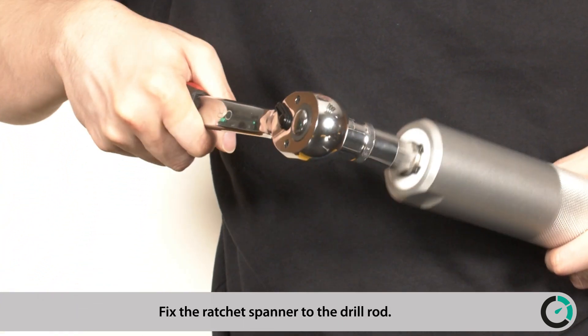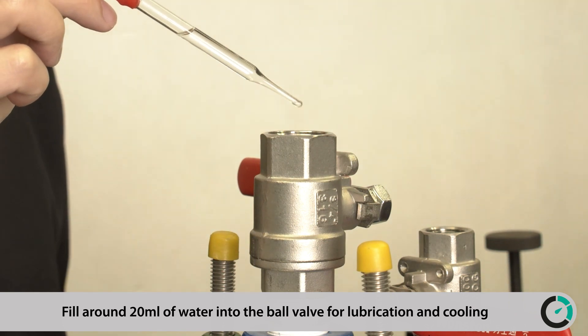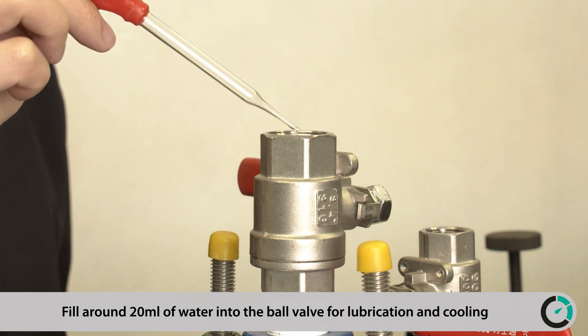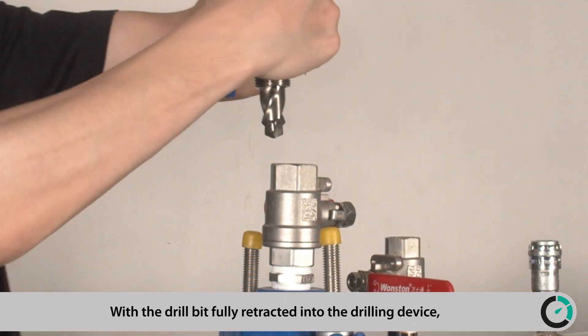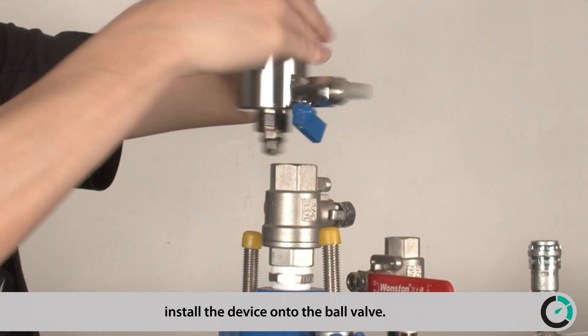Fix the ratchet spanner to the drill rod. Fill around 20 milliliters of water into the ball valve for lubrication and cooling. With the drill bit fully retracted into the drilling device, install the device onto the ball valve.